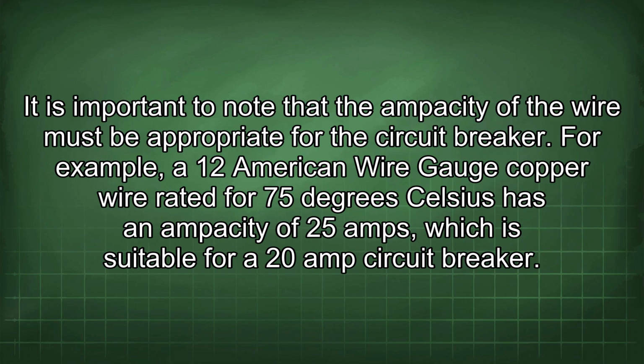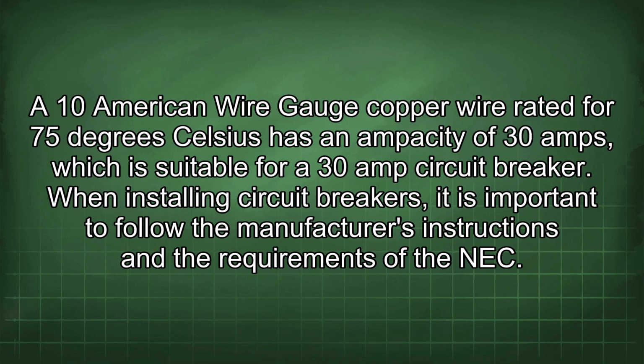It is important to note that the ampacity of the wire must be appropriate for the circuit breaker. For example, a 12 American wire gauge copper wire rated for 75 degrees Celsius has an ampacity of 25 amps, which is suitable for a 20 amp circuit breaker. A 10 American wire gauge copper wire rated for 75 degrees Celsius has an ampacity of 30 amps, which is suitable for a 30 amp circuit breaker.